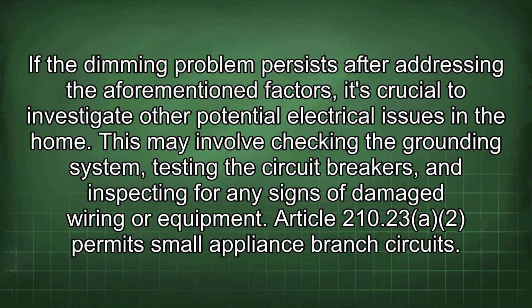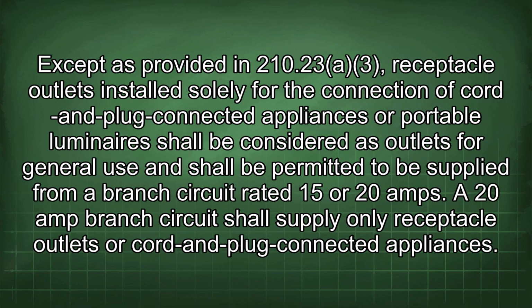Article 210.23(A)(2) permits small appliance branch circuits, except as provided in 210.23(a)(3). Receptacle outlets installed solely for the connection of cord and plug connected appliances or portable luminaires shall be considered as outlets for general use and shall be permitted to be supplied from a branch circuit rated 15 or 20 amps. A 20 amp branch circuit shall supply only receptacle outlets or cord and plug connected appliances.